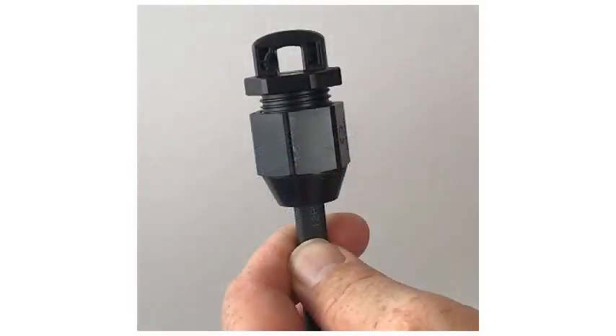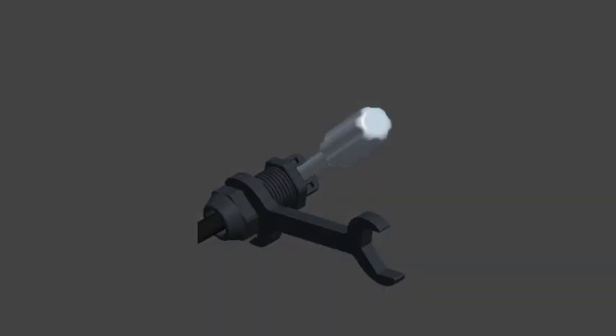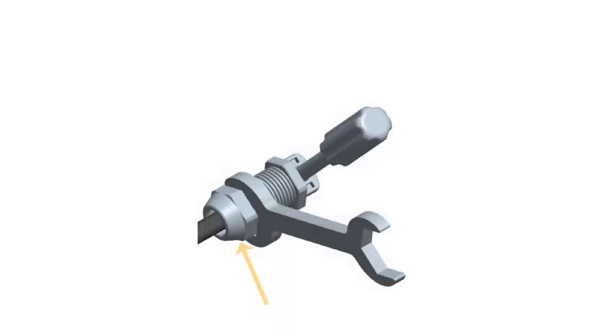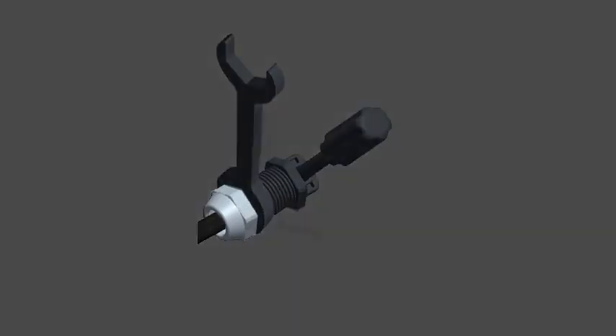Make sure that the hex nut is fully tightened. Hold the Terminator body stationary with the screwdriver and turn only the hex nut to prevent the conductors from twisting out of the separator. Be sure to only tighten the hex nut. Rotating the Terminator body could cause the conductors to back out past the internal separator.